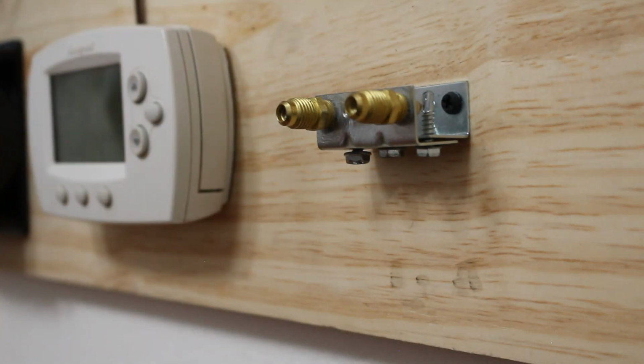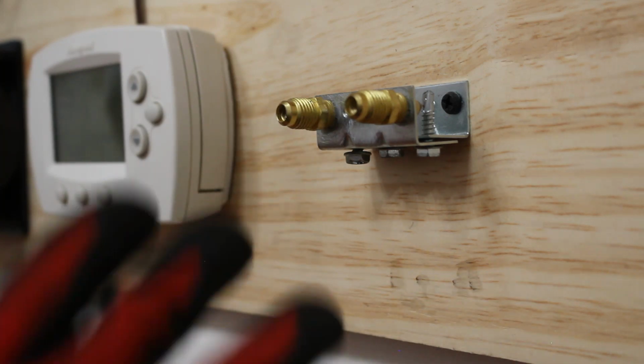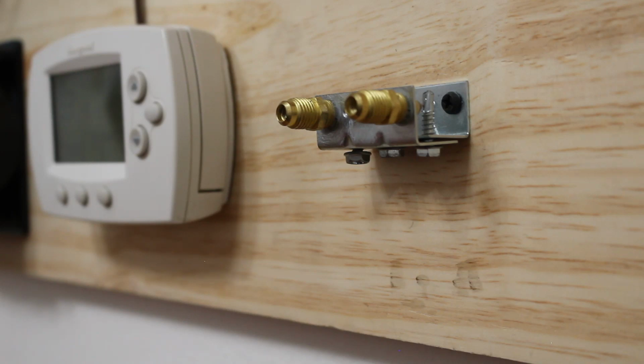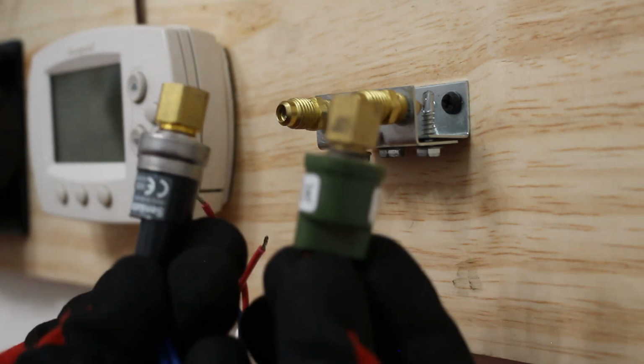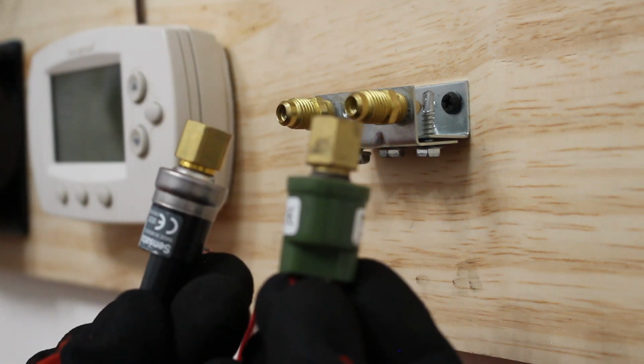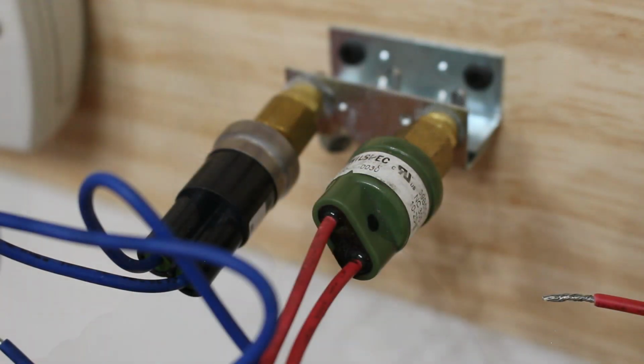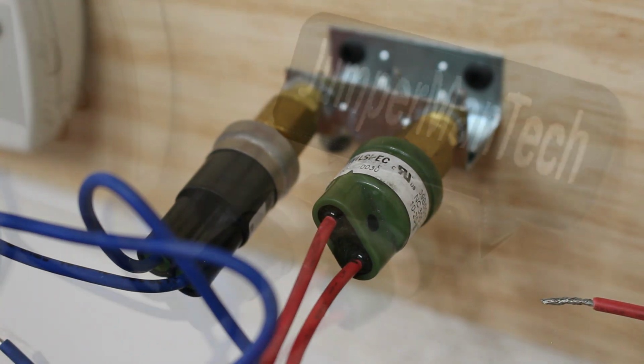Let's say we recovered the refrigerant from the system. We have two Schrader valves at these points. We're going to install our swivel T's, and then from there, we're going to screw on our pressure controls. Of course, let's pretend we have our swivel T's on, and now we have these mounted. From here, we can pressurize the system, check for leaks, make sure there's no leaks. From there, we can pull a vacuum and then charge the fresh refrigerant. From this step, we're going to wire these up.